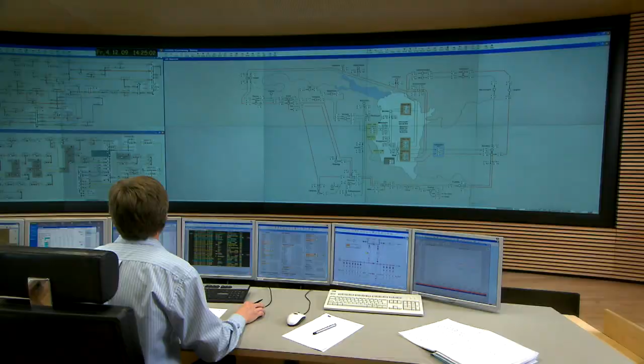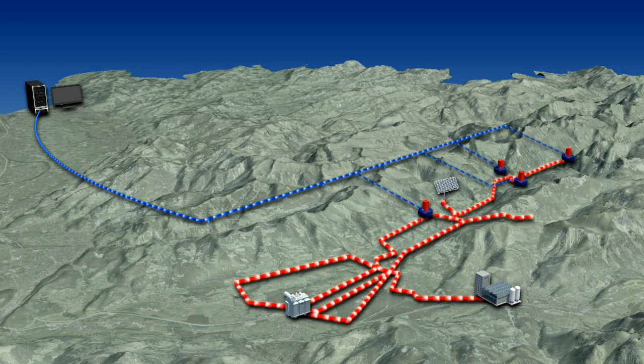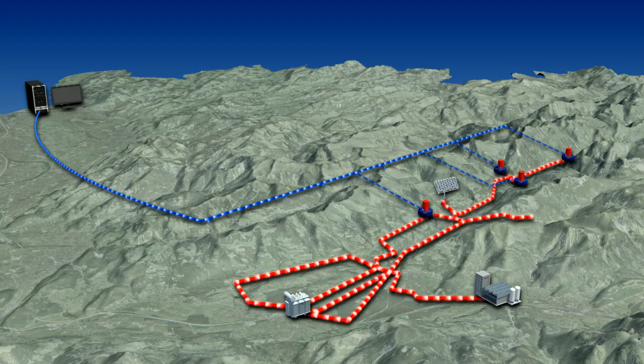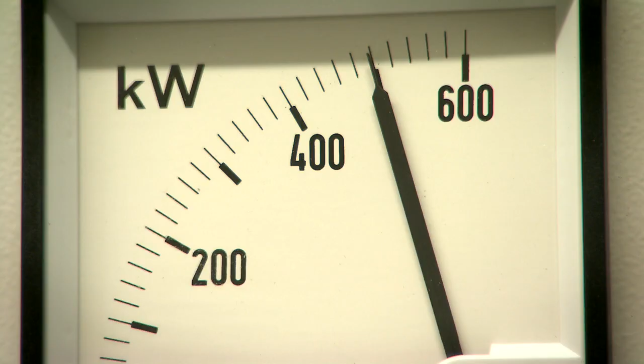Additionally, the synchronous generators of the small hydropower plants can be accessed in their reactive power management to support the system. In the process of this coordinated voltage control, the CVCU sends adjusting commands to the power plants. In this way, a maximum of existing grid reserves may be accessed.